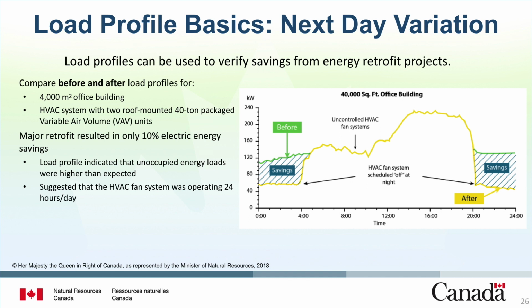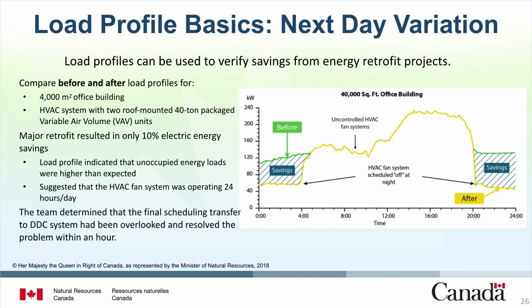One component of the retrofit was to upgrade the pneumatic controls to a direct digital control, or DDC, system. The energy manager contacted the property manager and HVAC controls contractor. Together, they determined that the final transfer scheduling to the DDC system had been overlooked. The team resolved the problem in under an hour and realized the project's anticipated savings.